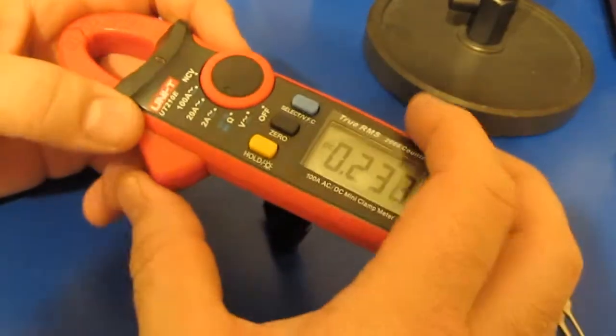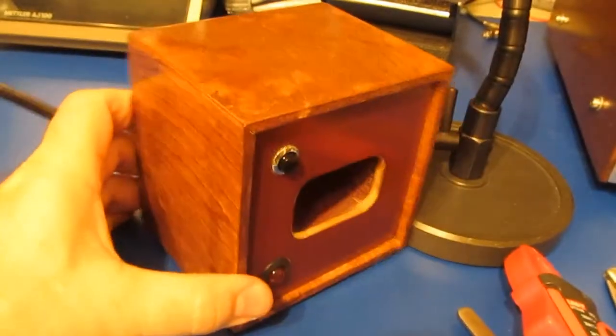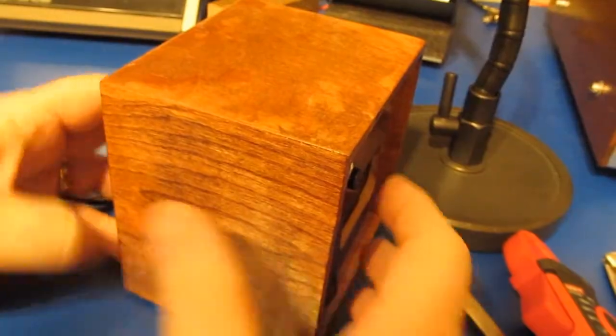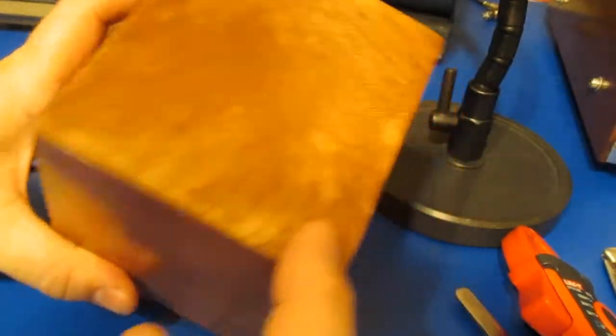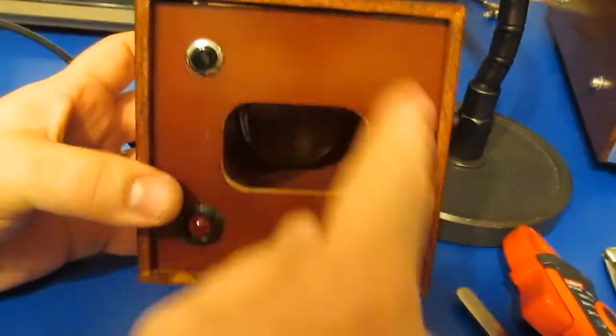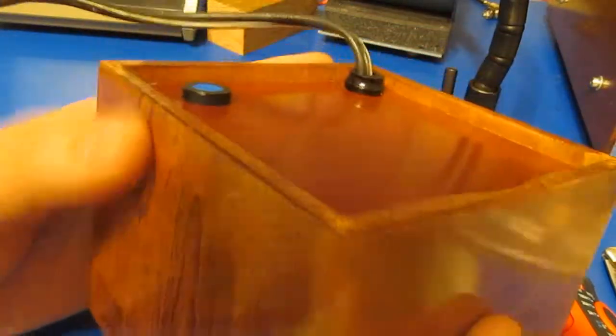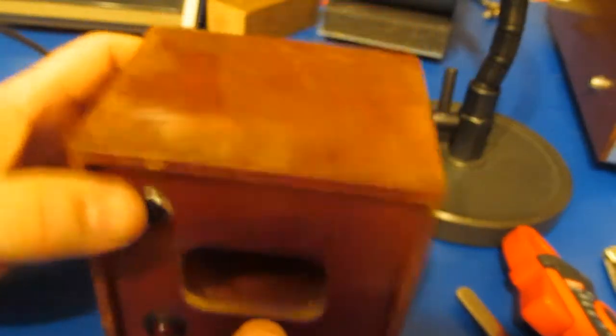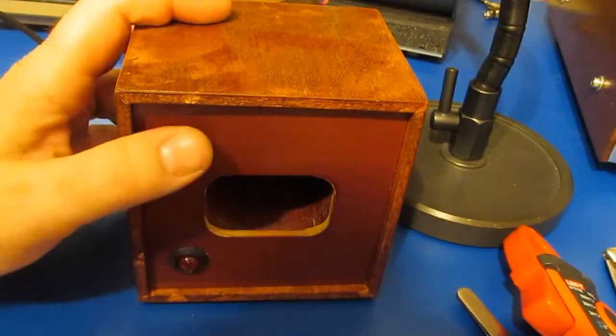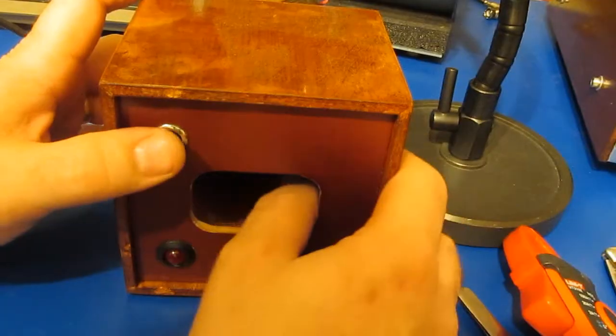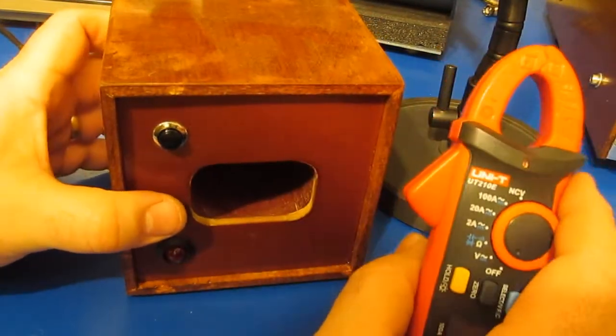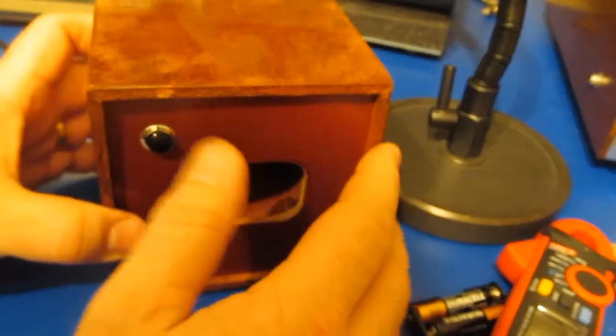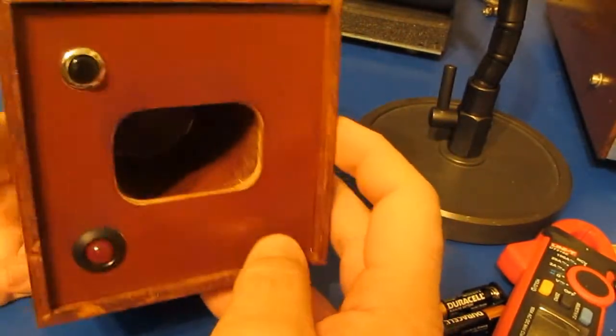The problem first is we have to get rid of any residual magnetism. And the way that we do that is we use a degauss coil. So this is one that I had made. I showed this in a previous video, but I did not show it once it was completed. You can see there's quite a few coats of polyurethane on this. But it's essentially a coil. This is built up on some phenolic tube. You can see this just runs off the 120 volt standard AC line. There's a fusing line with it and on the inside there's a PTC that's in series with this switch. And then this light is across the coil. You basically install the probe into this area here. Push the button and this will put out a magnetic pulse that sits there and oscillates. And that will erase any kind of residual magnetism that's in the probe head. And after that, then we can go ahead and try to do the alignment. So again, if you're interested in seeing what this looks like on the inside, you can watch the other video.